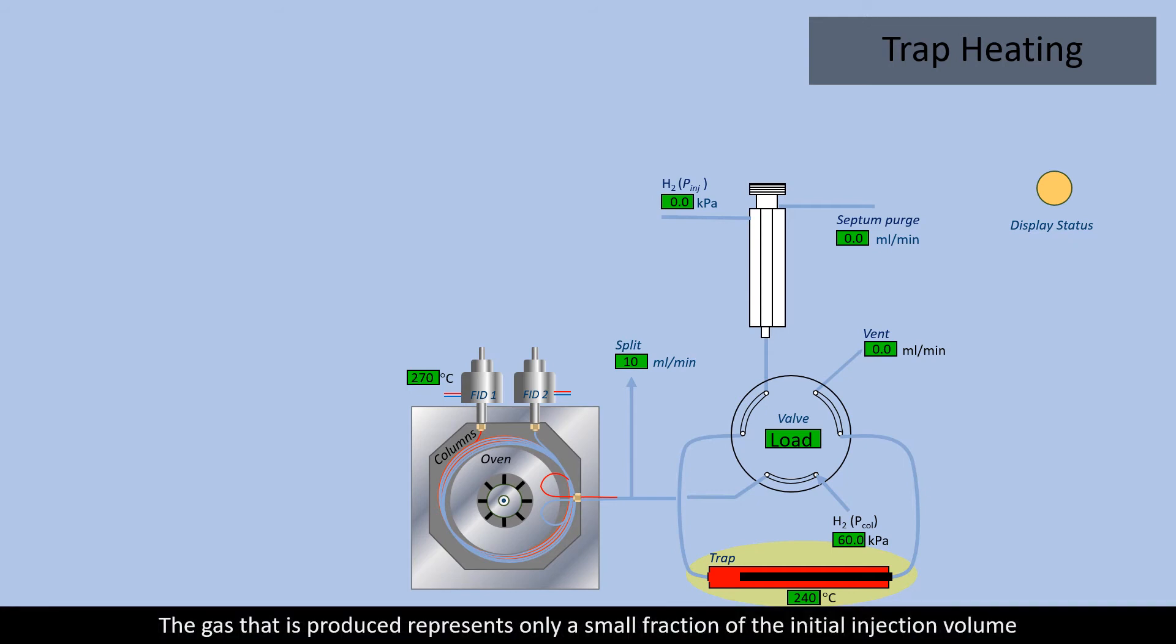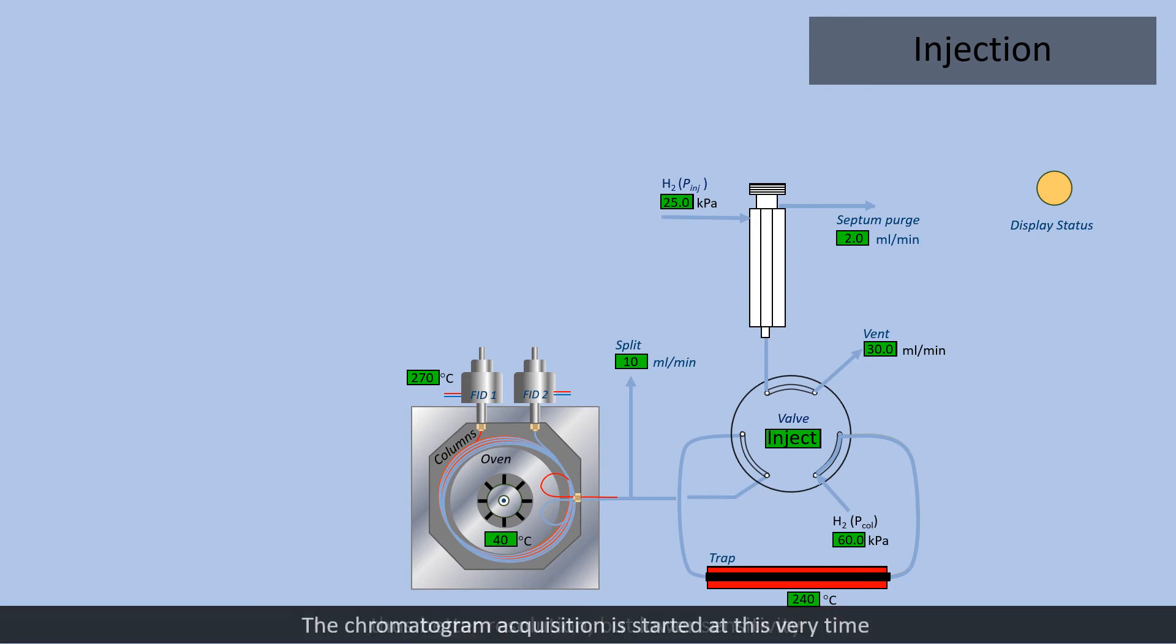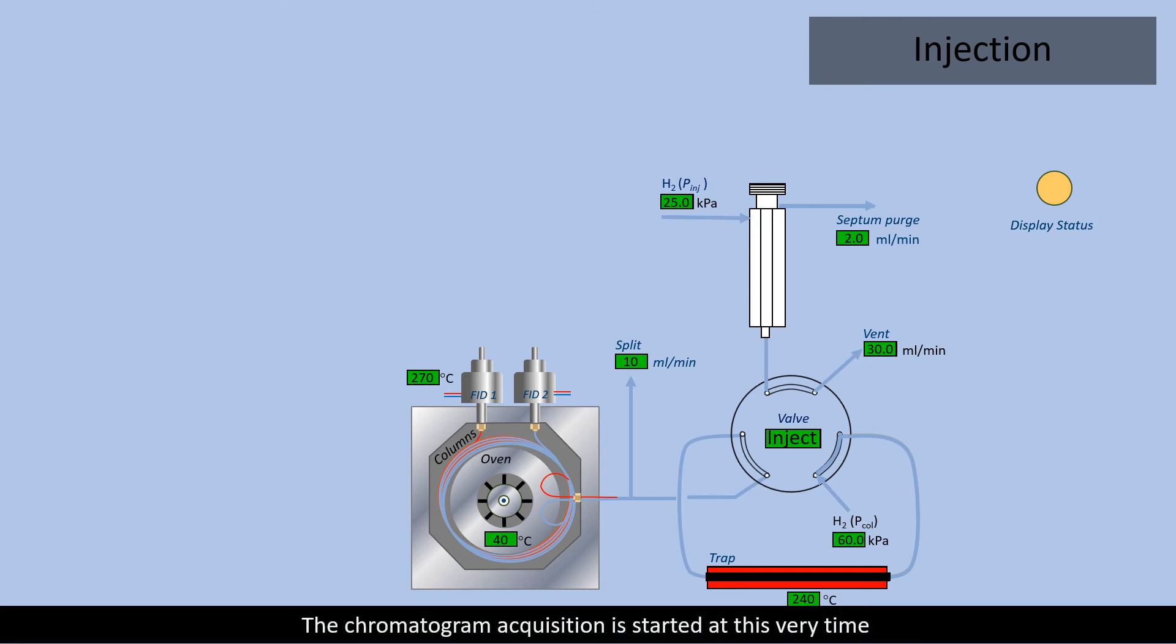The gas that is produced represents only a small fraction of the initial injection volume. Then, the heated valve is turned to inject this gas concentrate into the two columns under a flow of hydrogen. A fraction of this concentrate is directed to the split to give thinner peaks, thus better resolution but lower sensitivity. The chromatogram acquisition is started at this very time.